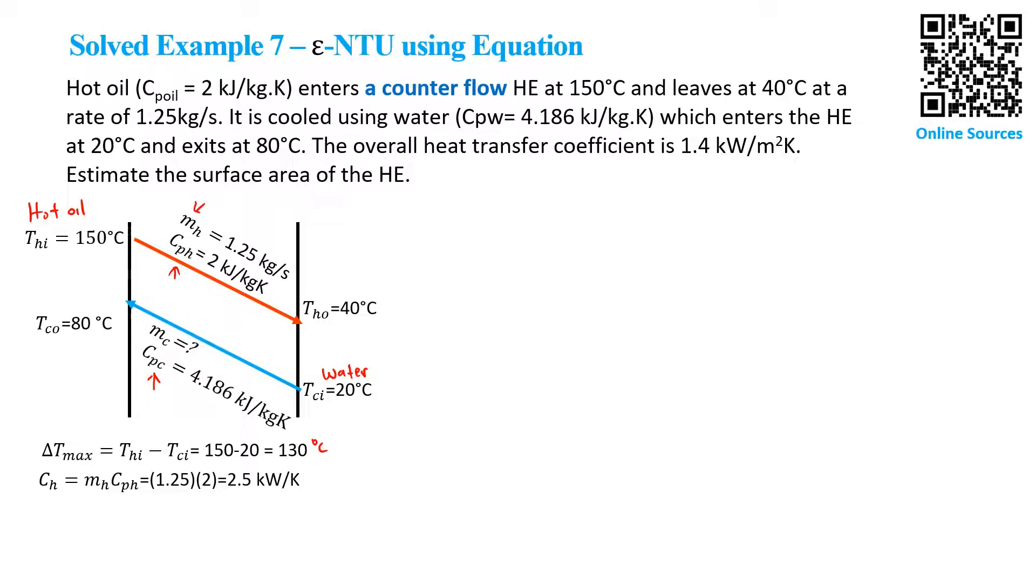We use the normal equation. Q_actual equals CH times ΔTH. We find Q_actual = 275 kW, and from that we can calculate mC. mC equals Q divided by CP of cold water divided by ΔT water, and we find mC = 1.1 kg/s.